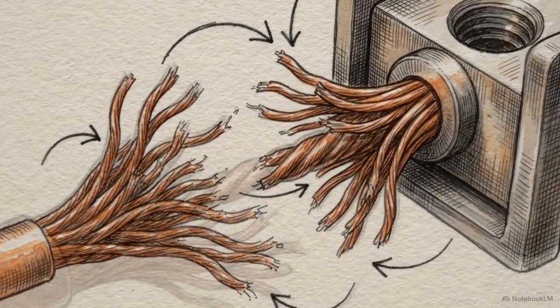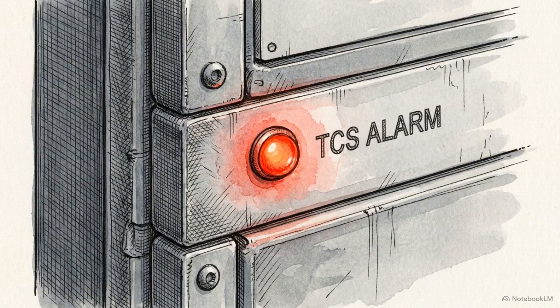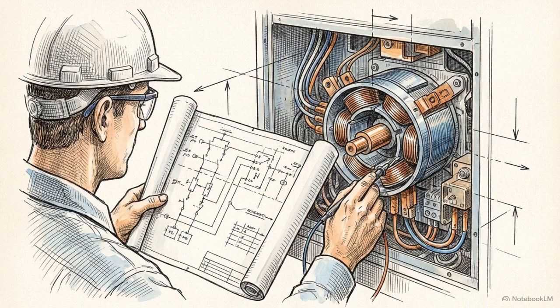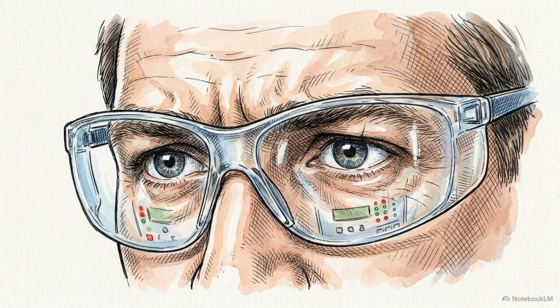path. Similarly, a flashing trip circuit supervision alarm requires active tracing. Technicians must pull the schematics and follow the DC supply wiring point to point, checking for blown fuses or degraded trip coils on the physical breaker mechanism. Commissioning engineers must trust their first principles. When digital results don't match the raw physics of the panel, the physical layer is almost always the culprit.